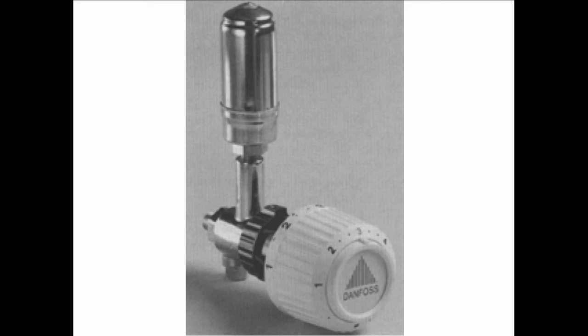But when the steam condenses, it shrinks, and the air will come right back into the building through the air vents. Now, if we've got the air vents sealed by the thermostatic radiator valve, because we don't want the room to get any hotter, the vacuum that's going to form inside the radiator due to the condensing steam will draw more steam into the radiator. So we need a vacuum breaker on the bottom. So as soon as steam begins to condense in the radiator, the vacuum breaker senses that drop in pressure and lets air back into the radiator, and that's the way you keep a radiator from overheating.